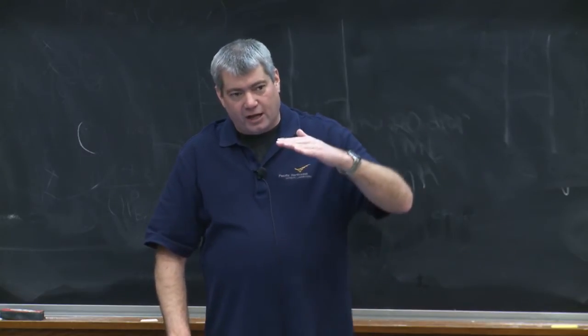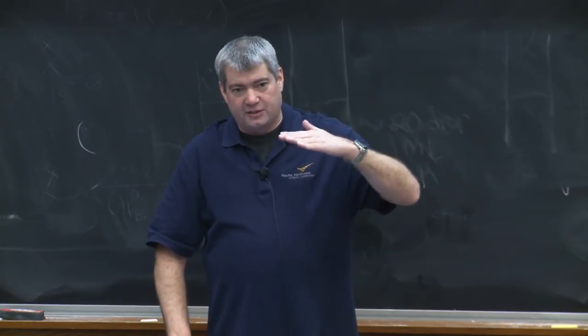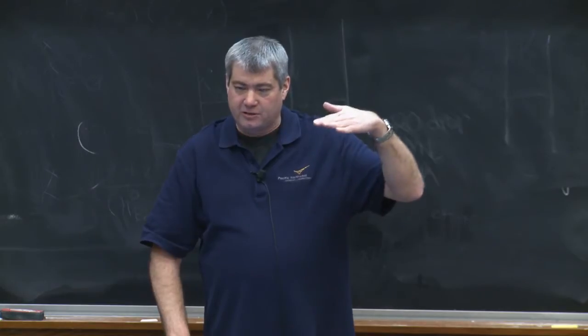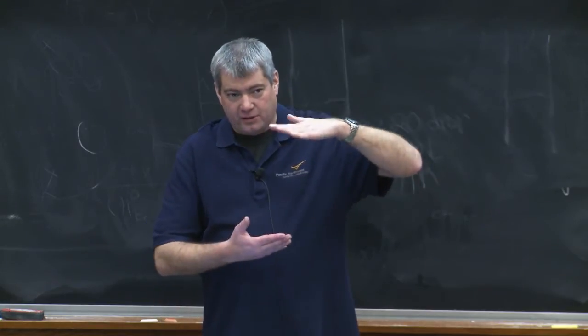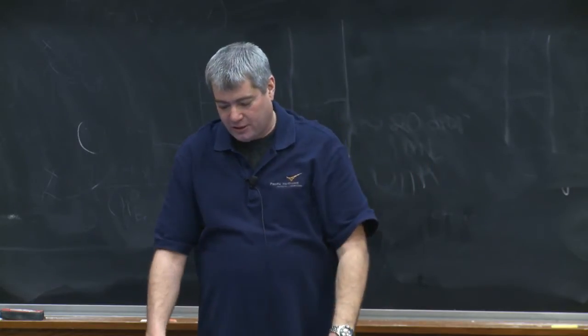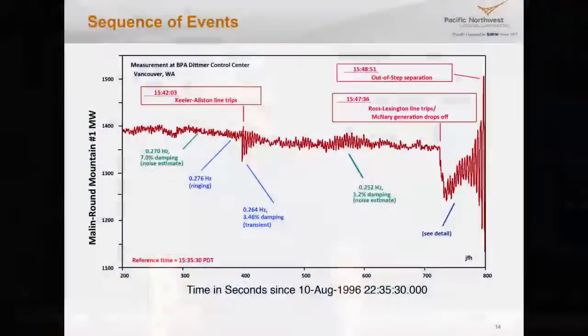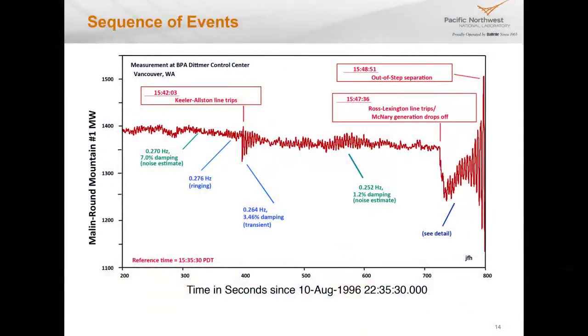A heavily loaded line heats up the more current it carries. The current flowing through the wire heats the wire and it sags. So a heavily loaded line will sag into those trees underneath it. That particular line tripped. It was within its rating. The trees were just too tall. And then about 5 minutes later, we lost another 345 kV line, and then the system went unstable. These are growing oscillations here, electromechanical oscillations.